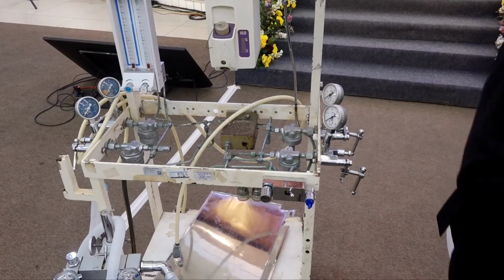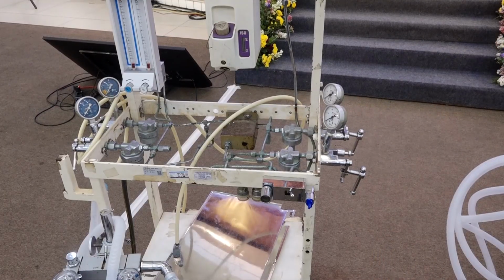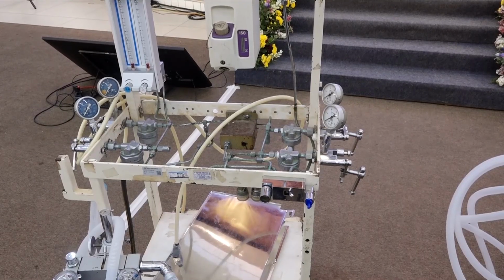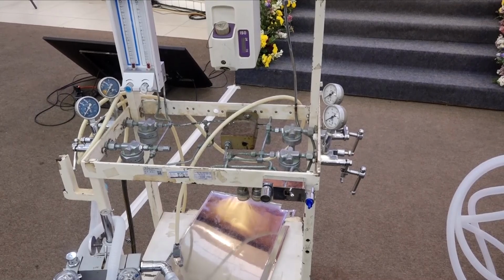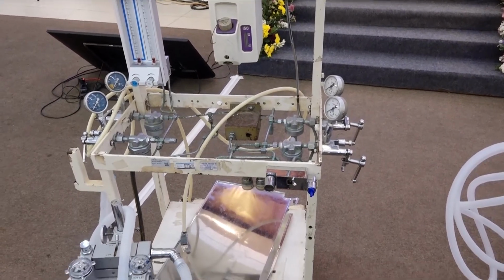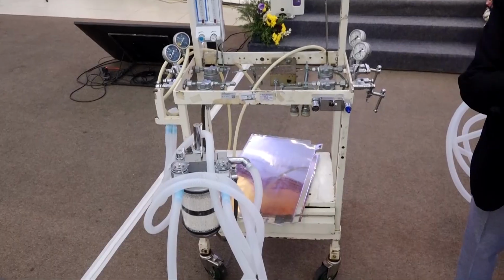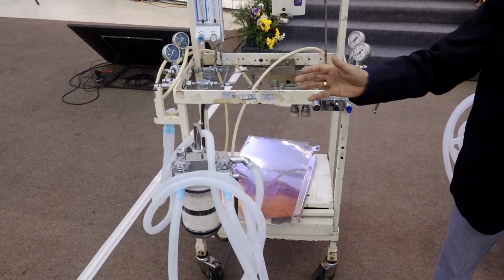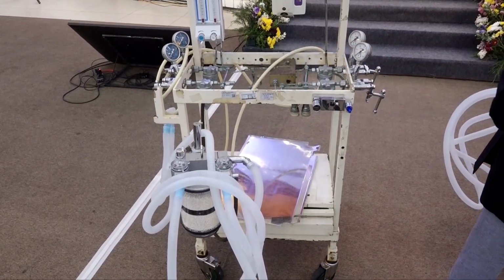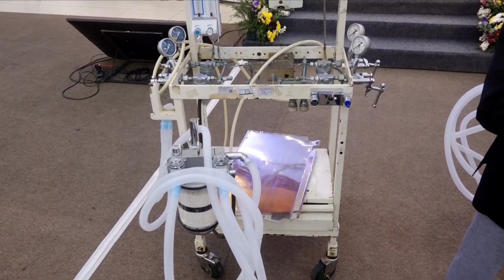In the newer machines or in the workstations, this has been replaced by fail-safe valves. I'll come to fail-safe valves when I discuss the intermediate pressure system, because that will be there. These fail-safe valves are there between the pressure regulator and the flow control valve. So in between, the master and slave mechanism is not there. We have the fail-safe valves. Okay, now this is about the high pressure system. We'll talk about the intermediate pressure system.